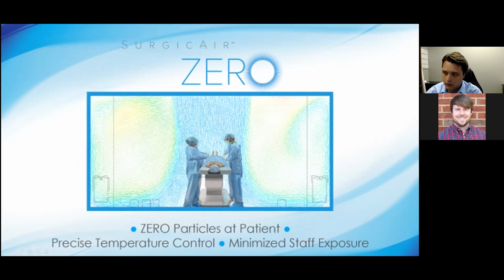This is what the airflow looks like with the Surgic Air Zero system. Now, all the contaminants that are in the space can't get into that room, because since we're tripling the airflow into the space, we're reducing that delta T, or the temperature difference between the supply air and the room air. Now, instead of delivering air at 10 or 12 degrees colder, we're only delivering it at 2 or 3 degrees colder, eliminating that effect of gravity and the entrainment problem, and maintaining this wide zone of clean air throughout the entire surgical area. The added benefit here is, since this air is warmer, it's actually warmer air hitting the patient, reducing the risk of hypothermia for them, and it's actually cooler air actively hitting the surgical team, meaning they're more comfortable and the patient is safer.